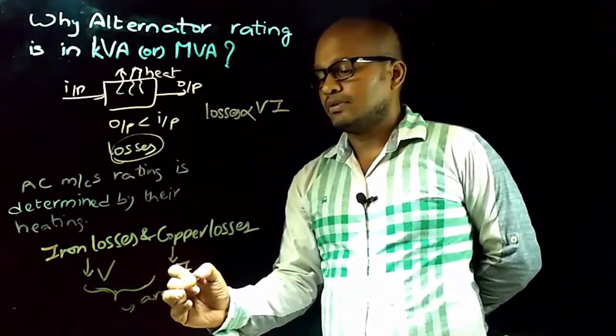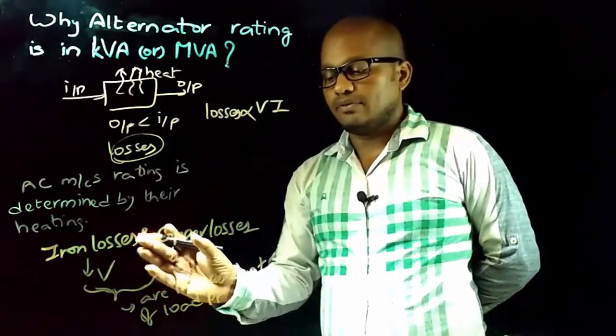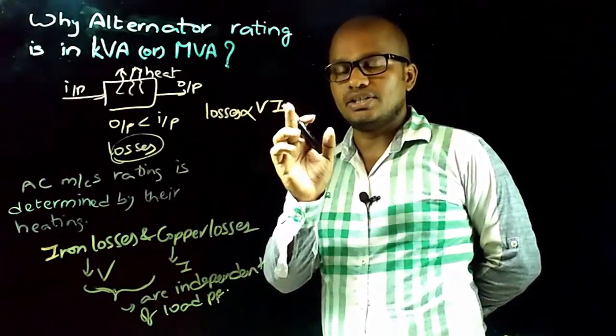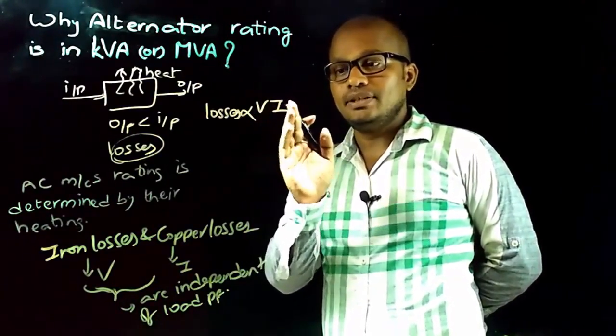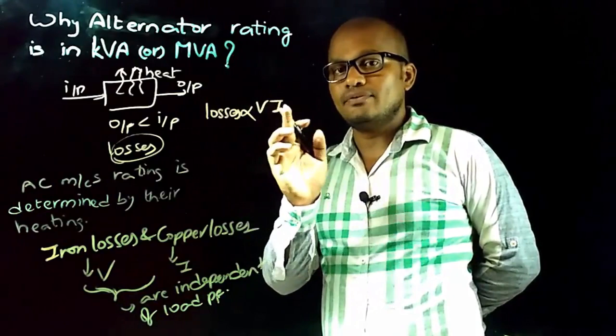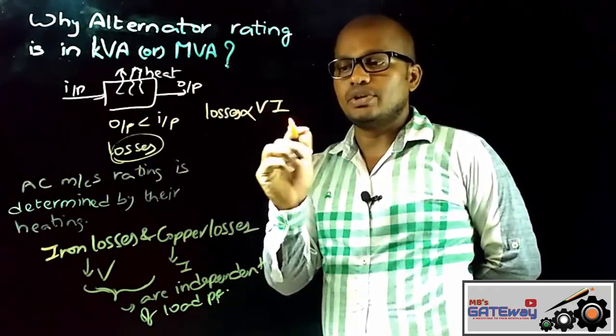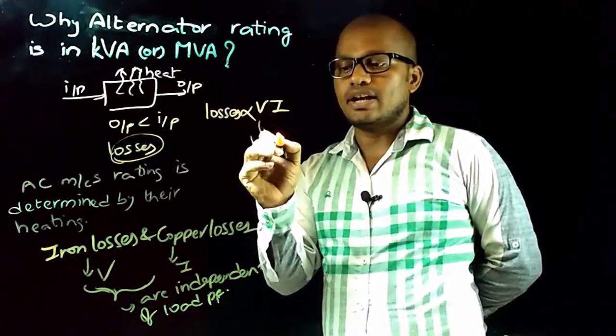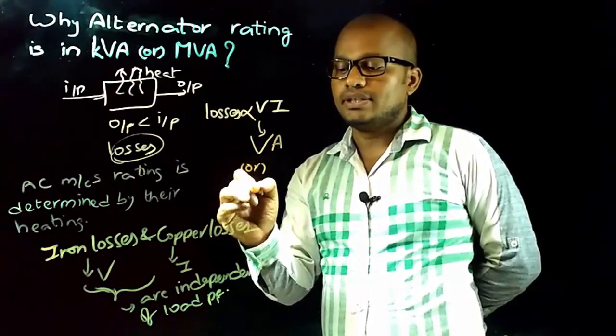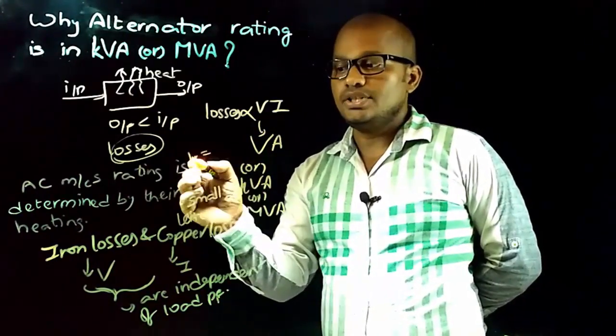Since these losses are independent of load power factor, if losses were dependent on power factor, then losses would be proportional to V×I×cos(φ), which represents real power P = VI cos φ, and the rating would need to be in kilowatts. But because losses are independent of power factor, losses are directly proportional to V×I only, so the rating of the alternator is in VA, KVA, or MVA.